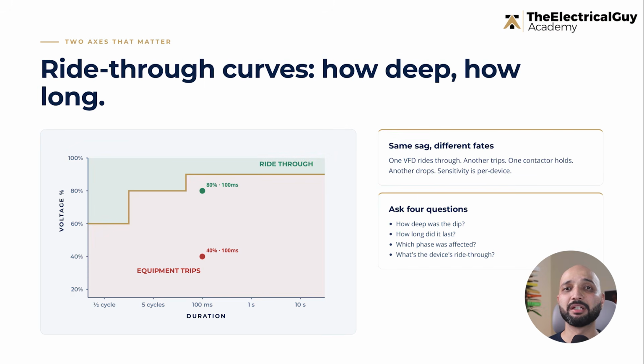This is why equipment sensitivity is usually studied using voltage ride-through curves. A voltage ride-through curve tells us how much voltage drop equipment can tolerate and for how long. Some equipment is sensitive mainly to voltage magnitude. For example, undervoltage relays or some contactors may trip when voltage falls below a certain level. Some equipment is sensitive to both magnitude and duration. Electronic power supplies, PLCs, and drives often behave like that. They may tolerate a very short dip, but if the dip lasts longer, their internal DC voltage fails and they trip. This is why two pieces of equipment may behave differently during the same voltage sag.